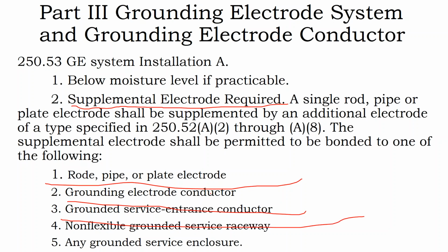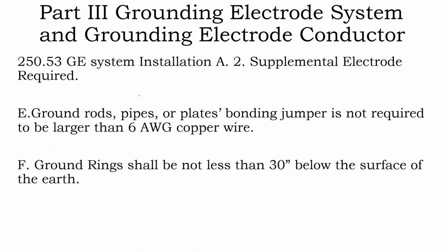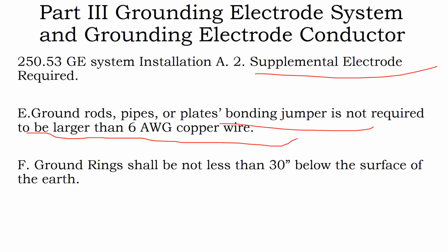So, you might be required to put in supplemental grounding electrodes, with separate requirements for what constitutes a supplemental electrode, and there might be a little bit more leeway in there than in your primary electrode. But again, your ground rods, pipes, or plates bonding jumper is not required to be larger than number 6. So if you're using a ground rod or a ground pipe or a plate, that bonding jumper is not required to be larger than number 6. So it's very common, given that there's that number 6 bare copper wire up to the rooftop requirement, just to run number 6 bare copper up to the roof from your ground rod as a common design requirement.